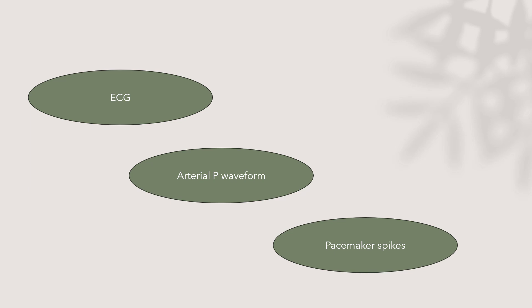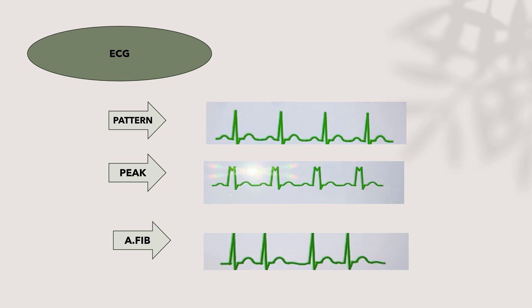The most important triggers are ECG, arterial pressure waveform, and pacemaker spikes. The ECG is the best trigger — better than arterial pressure waveform — because the electrical impulse precedes the mechanical impulse. There are three ECG trigger types. The first is the pattern type, which is the preset default mode: the computer analyzes the height, width, and slope of the positively or negatively deflected QRS complex, giving good timing for balloon inflation and deflation.